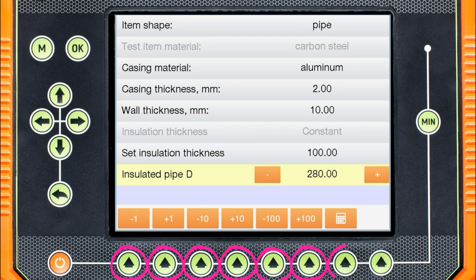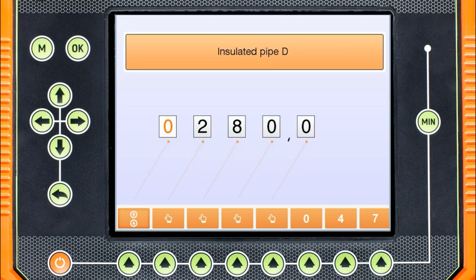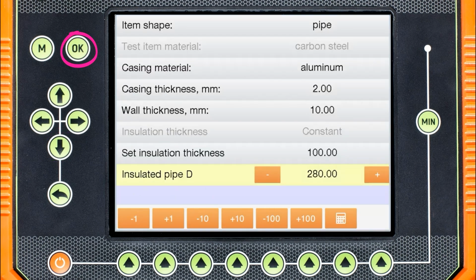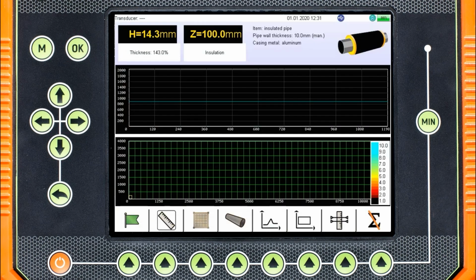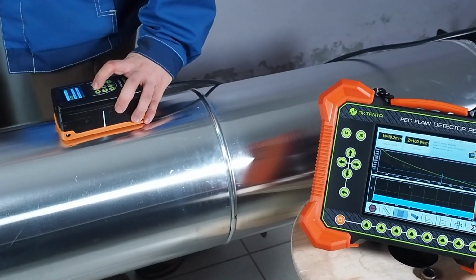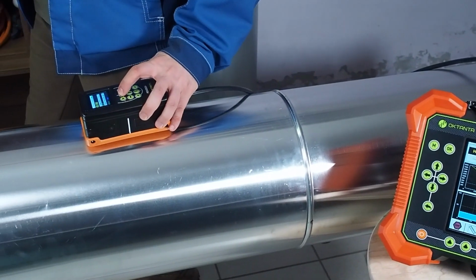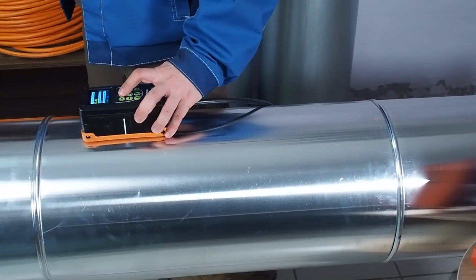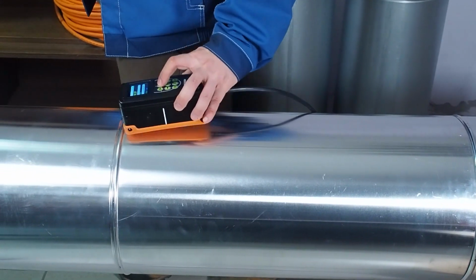We recommend taking these parameters from the item data sheet or, if possible, determining them directly at the point of calibration. The device does not require absolute accuracy in setting all these parameters and will operate correctly even, let's say, with an insulation thickness error of 20%.